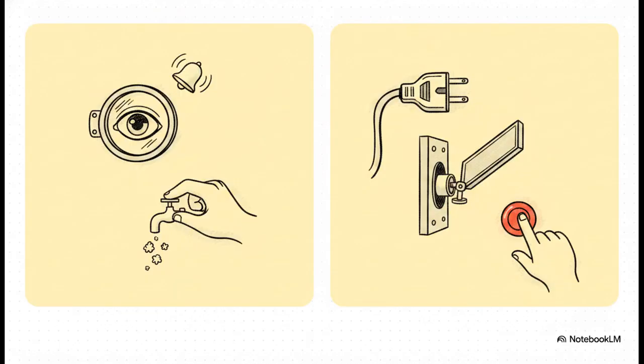And the operational response for these two states is totally different. An alarm means operators need to actually walk up to the device, look through the inspection window, and use a built-in extraction valve to safely pull out that accumulated gas so they can analyze what's causing the fault. But a trip state means the relay just physically intervened to save the grid from an imminent explosion. The power is cut, and operators have to thoroughly investigate. Interestingly, if that flap valve is triggered by a massive surge, it actually locks itself into place. An operator has to manually release it using a built-in test button once everything is finally safe to turn back on.